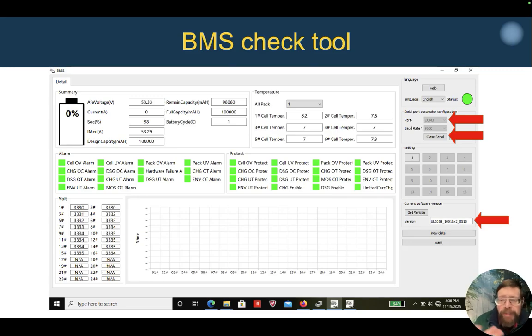When you open the BMS check tool, this is what you'll see. On the right side, there's a green light that'll be red initially. You'll need to select which COM port you're using, and then click where it says open serial, and it'll connect. The way to check if it really connected is not that this turns green, because it'll turn green even if it didn't properly connect.